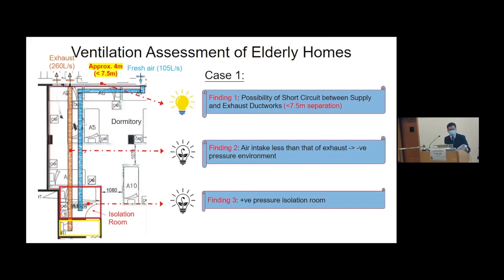there was adequate fresh air being supplied to the dormitory. However, the distance between the exhaust duct and the fresh air duct was found to be approximately 4 meters only, which is less than the 7.5 meters requirement, and there may be a possibility of short circuit between the ductworks. Also, the mechanical air intake rate of approximately 105 liters per second was found to be much less than the mechanical exhaust of approximately 260 liters per second.